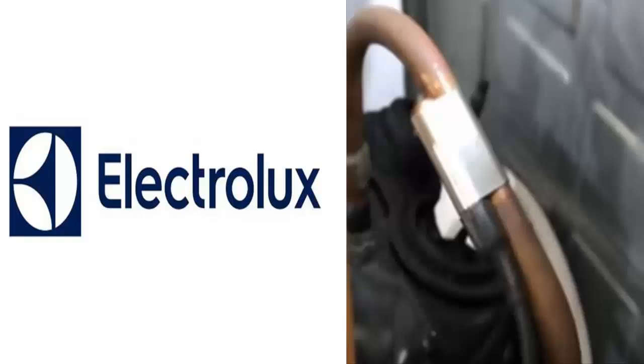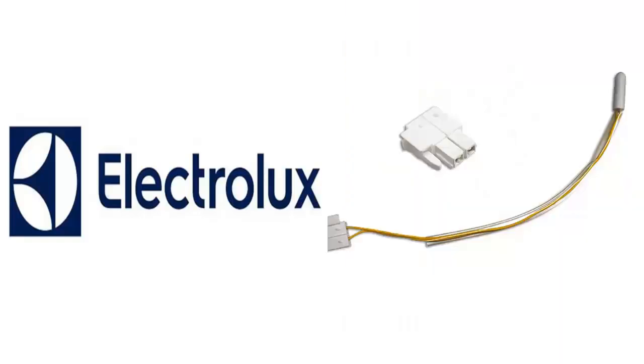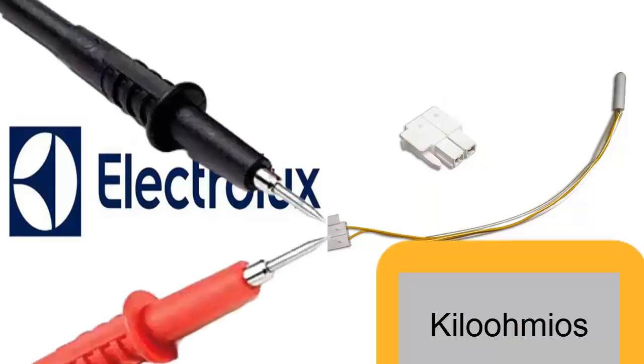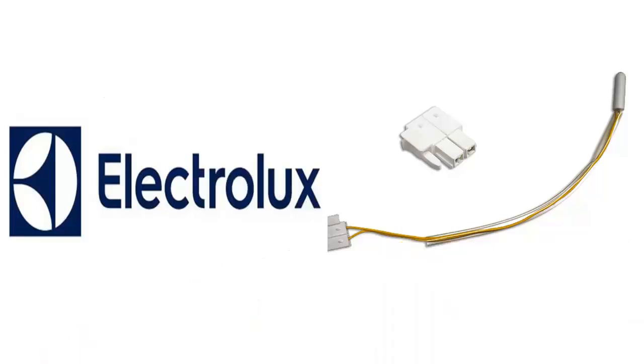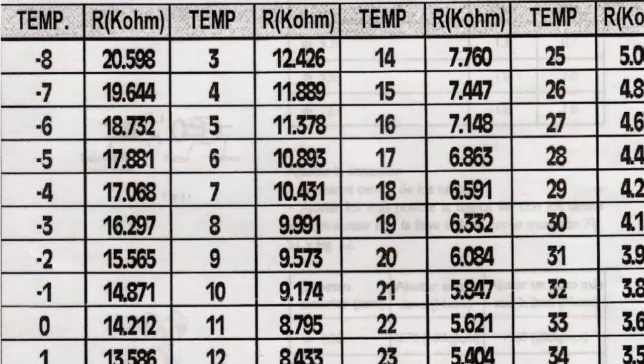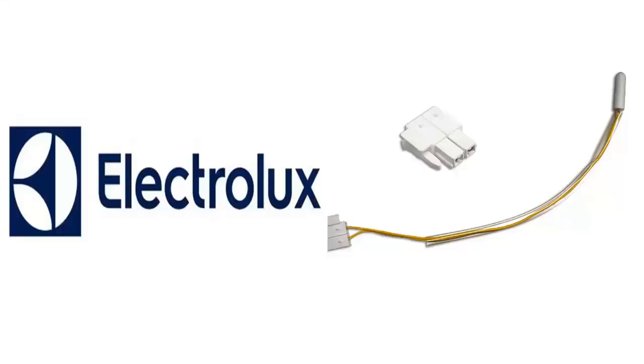If the problem is not found, disconnect the sensor from the electronic board and measure its electrical resistance with a multimeter set to the kiloohm scale. The electrical resistance value measured at the sensor should be neither zero nor infinite and should decrease when rubbing the sensor with your hand. If you have the sensor's resistance versus temperature table, compare the kiloohm value obtained on the multimeter with the value indicated in the table.